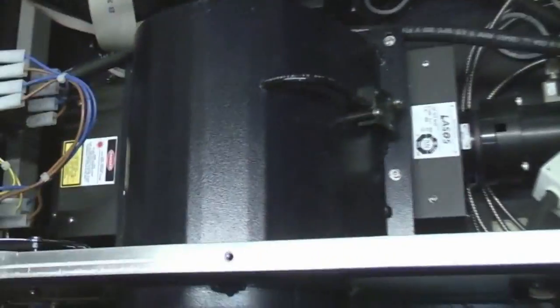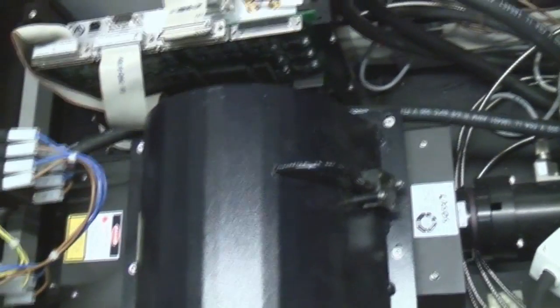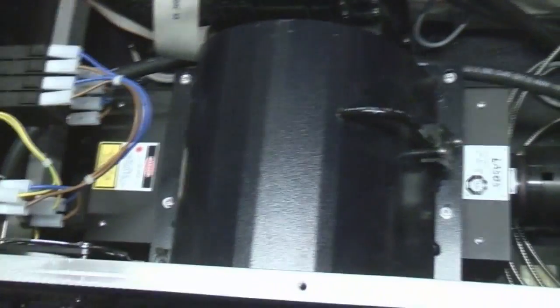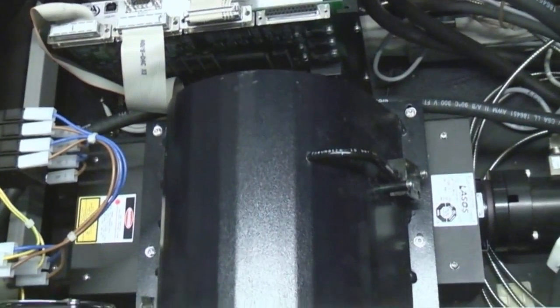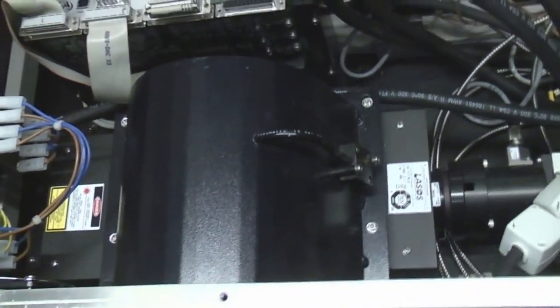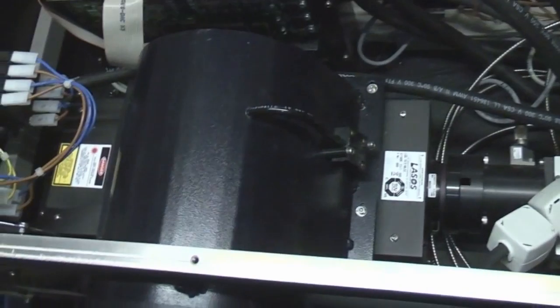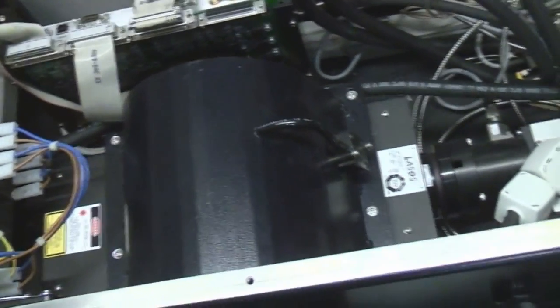So quickly go back to here. The one thing I thought almost certainly was in here was an argon laser, which is true. So this is the argon laser here, the main big rectangular casing. Argon lasers are getting pretty obsolete now because most of them have been replaced by solid state, but they're quite appalling because they take ridiculous amounts of power, typically about 1 kilowatt or so, to put out maybe 10 to a couple of 100 milliwatts of laser output.